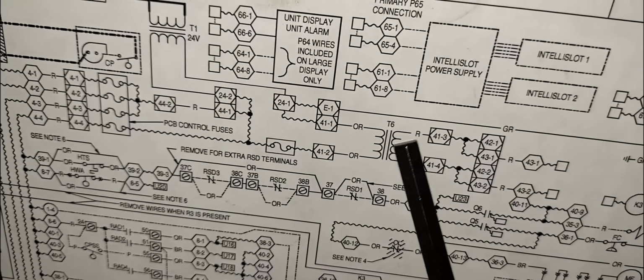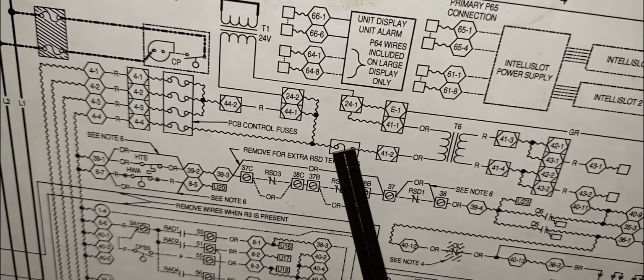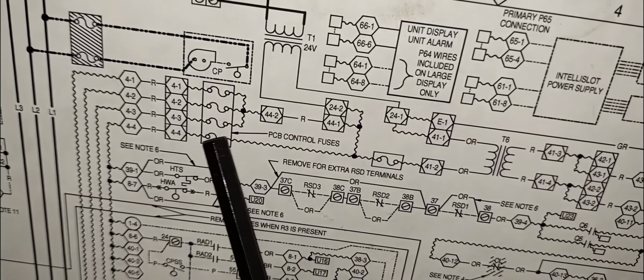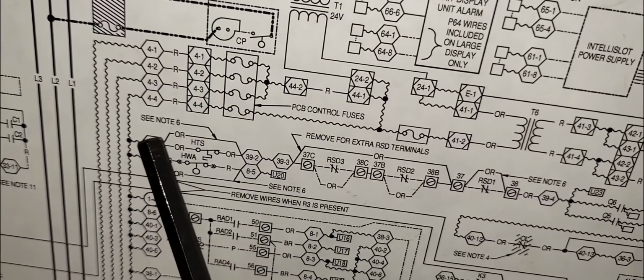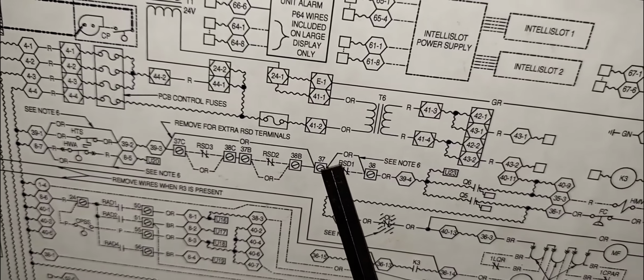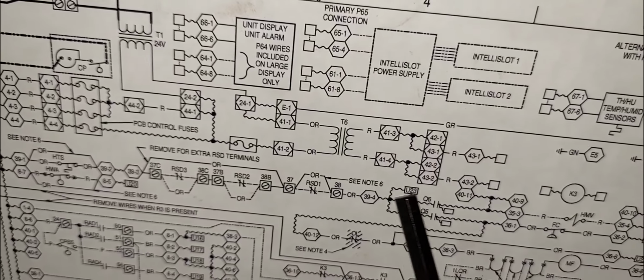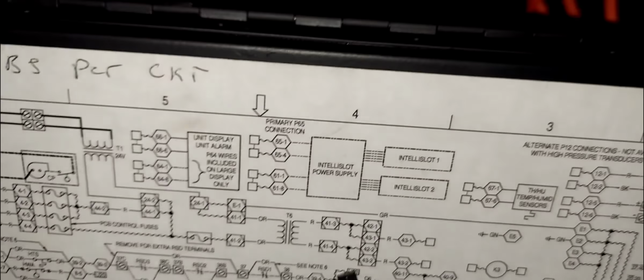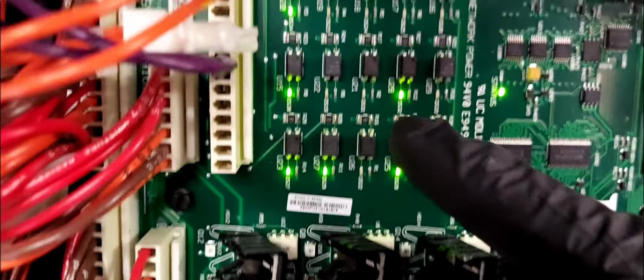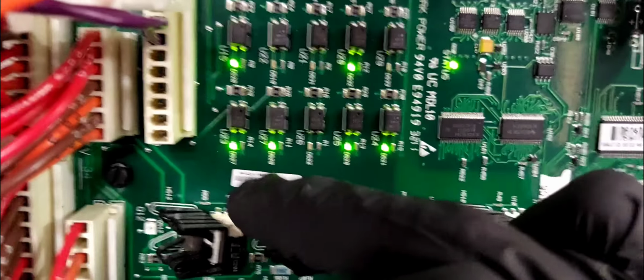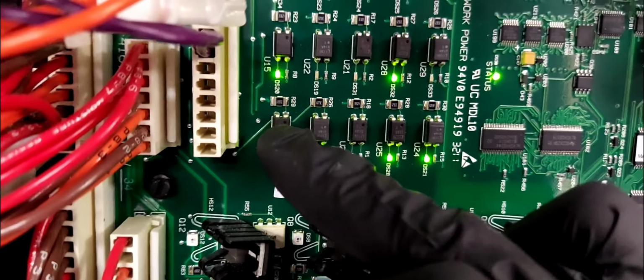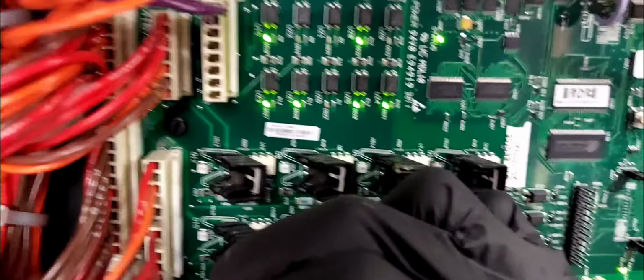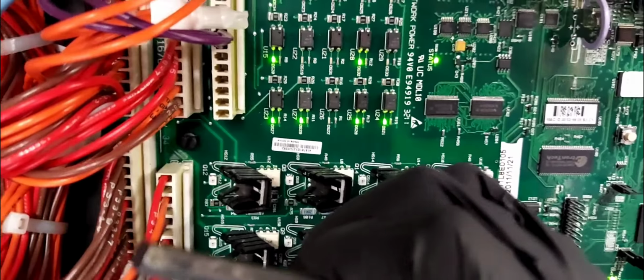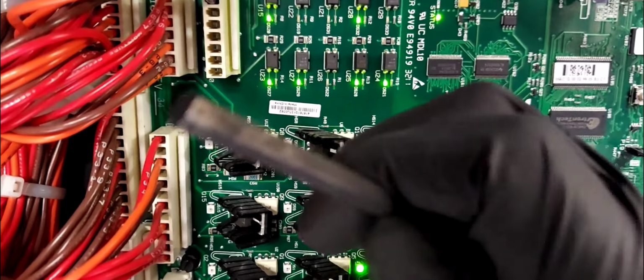If you're a pro, you will know this is a symbol for a transformer. 24 volts. If all your fuse is good, if this particular fuse right down here is closed or good, 24 volts is able to pass through all of this right here. And I had already verified that there's power on this line, because this input right here on the board, U23, is lit. So U23 is 22 right here, 23 right there. Okay, and there's a green light lit on that input. So if that green light is lit, that means 24 volts is there. So we're getting 24 volts.